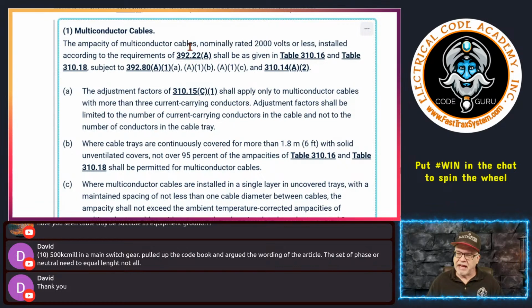Now, what that right there means is that's everything that we did in day 2, or part 2, when we sized the tray and determined whether the cables are going to be in a single layer, whether we have the larger ones, and then the smaller cables that are under 1,000 kcmil. We're saying that if we install the cables in that tray in accordance with 392.22(A), so you watched part 2 and you installed them properly, then the ampacity shall be based on 310.16 and Table 310.18.